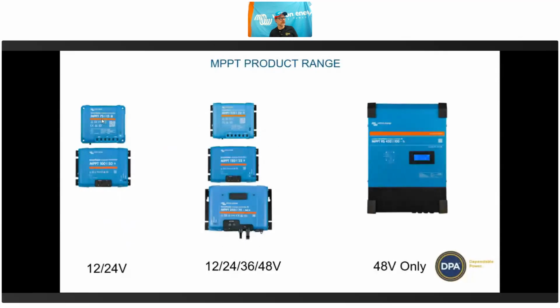So the 75 and the 100 range, they're suitable for 12 and 24. And then you've got the 100, 150, and 250 range, which is suitable for 12, 24, 36, and 48. And then you've got the 450 input range, which are only suitable for 48 volts.